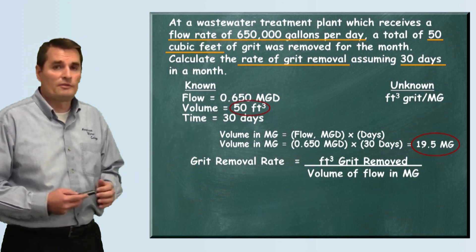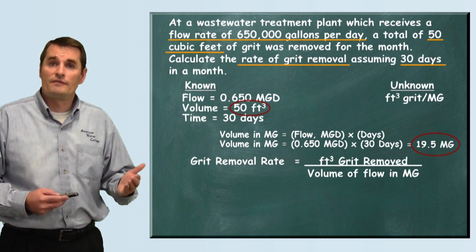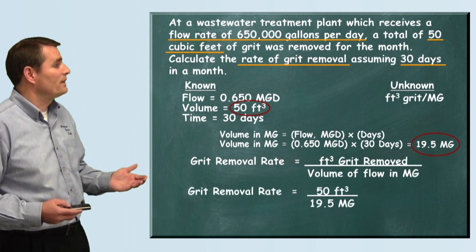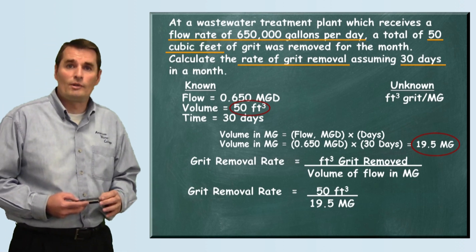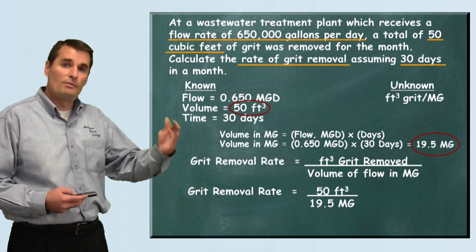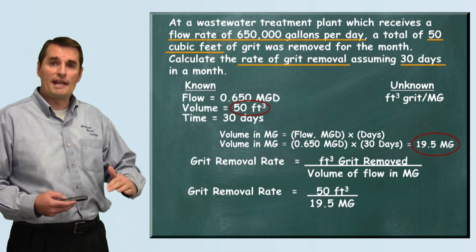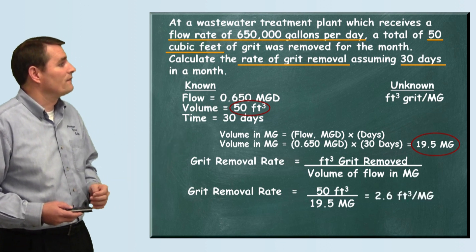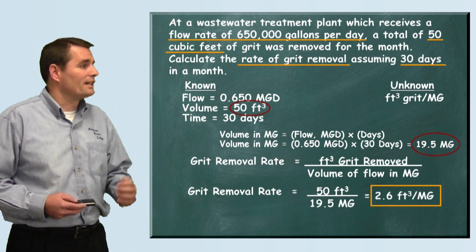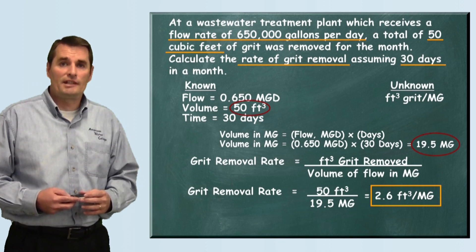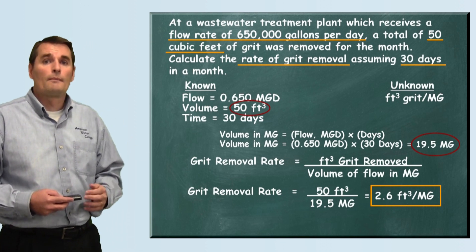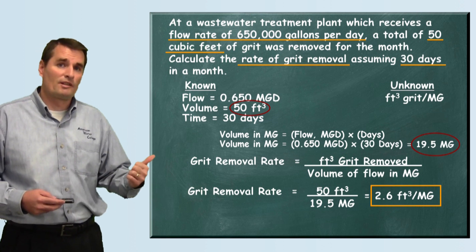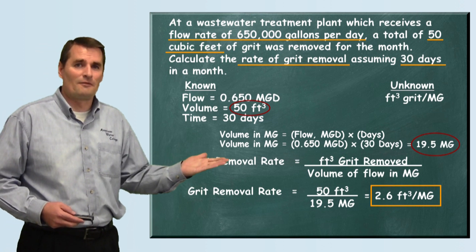They told us 50 cubic feet of grit was removed, so we put 50 cubic feet on top of 19.5 million gallons and do the math. When we divide 50 by 19.5, we get 2.6 cubic feet of grit removed per million gallons of flow. And that is how this problem is solved.